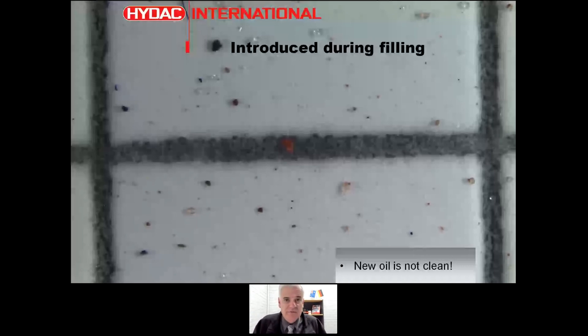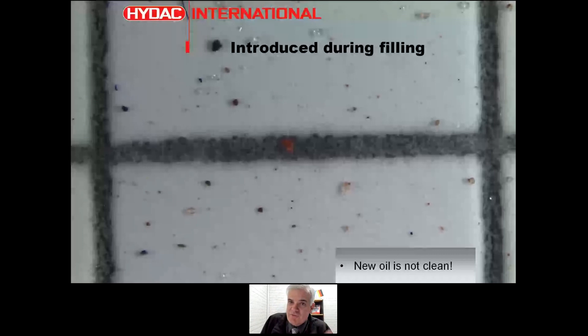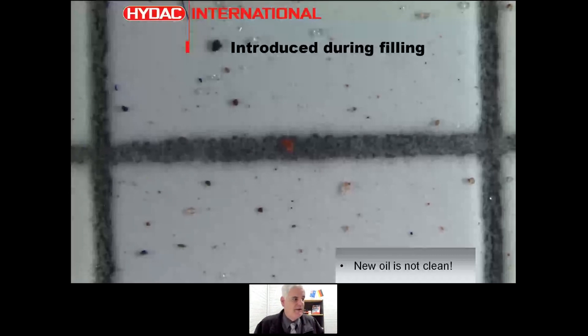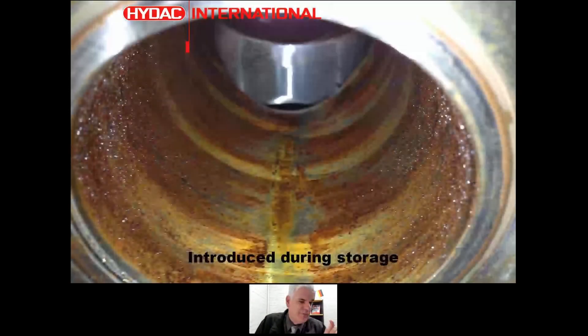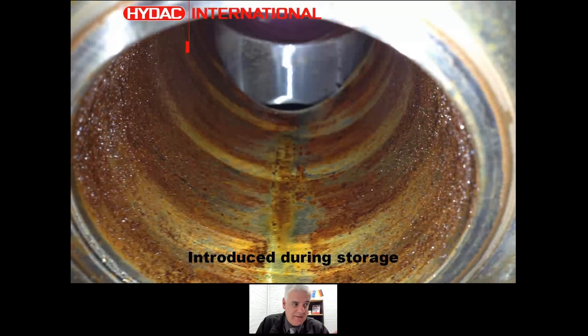It's absolutely critical that we are filtering the system with new, fresh, clean oil. As a rule of thumb, it costs ten times more to remove a contaminant from a system than it does to exclude it in the first place. That's why it's absolutely critical that we filter our oil before we put it in the system. We can damage a system by preparing it, making it, testing it clean, and then damaging it by putting it into storage.